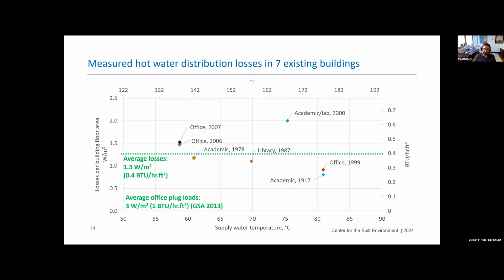And again, because these systems are operating many more hours than they really should be, they're servicing these distribution losses a large part of the time and operating the entire plant at really low loads, which is where boilers operate the least efficiently, right? So it's driving way more gas consumption than you would think for such a small load.